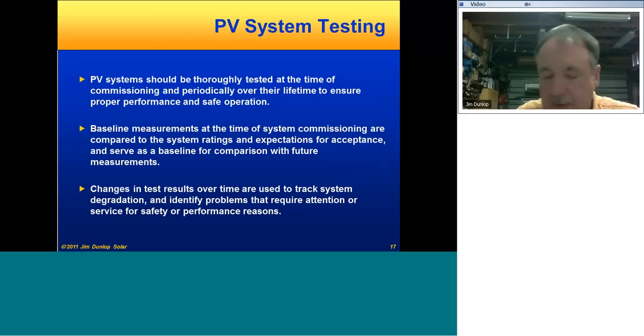If you have a fault developing in a source circuit, maybe there's no way to tell without going and doing insulation resistance tests on that source circuit or looking at how it's degraded over time.